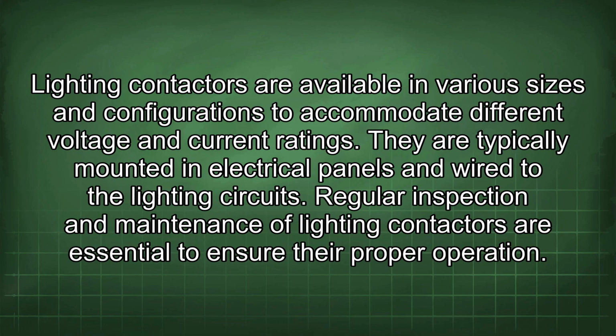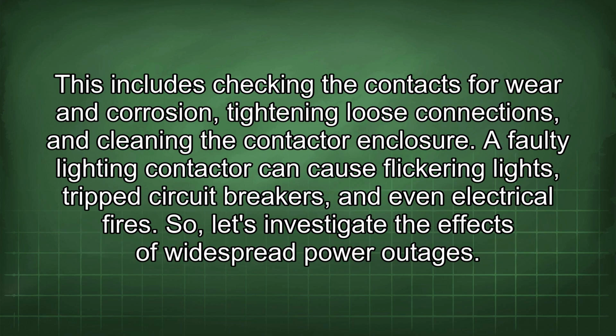Lighting contactors are available in various sizes and configurations to accommodate different voltage and current ratings. They are typically mounted in electrical panels and wired to the lighting circuits. Regular inspection and maintenance of lighting contactors are essential to ensure their proper operation. This includes checking the contacts for wear and corrosion, tightening loose connections, and cleaning the contactor enclosure. A faulty lighting contactor can cause flickering lights, trip circuit breakers, and even electrical fires.